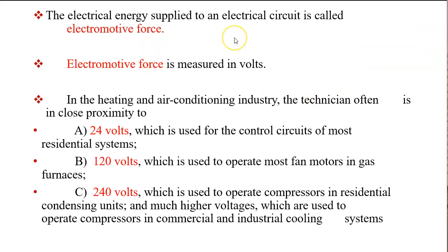Electrical energy supplied to an electrical circuit is called electromotive force, measured in volts. In the heating and air conditioning industry, the technician often is in close proximity to 24 volts. These are the voltages used in HVAC. Actually, there are three types: 24 volt, 120, and 240. 24 volts for the control circuit and the circuit board itself, 120 to control the fan, and 240 to control the compressor condensing unit with much higher voltage.